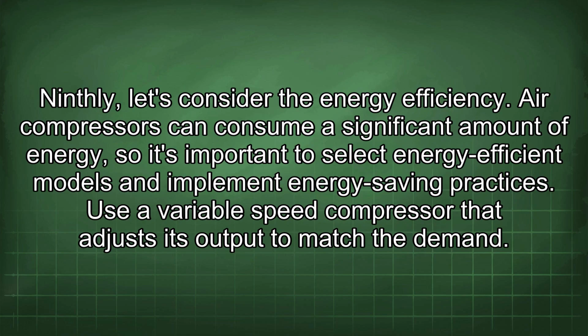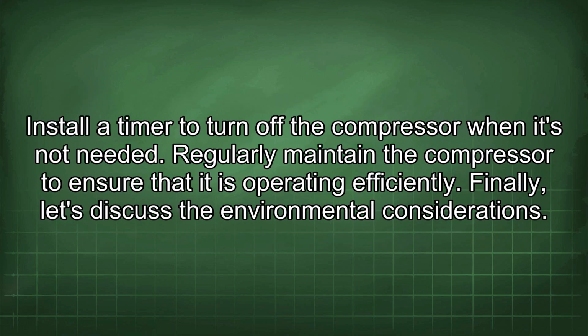Ninthly, let's consider the energy efficiency. Air compressors can consume a significant amount of energy, so it's important to select energy-efficient models and implement energy-saving practices. Use a variable speed compressor that adjusts its output to match the demand. Install a timer to turn off the compressor when it's not needed. Regularly maintain the compressor to ensure that it is operating efficiently.